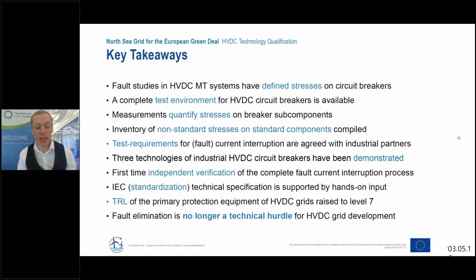And just to repeat, the 3 technologies of industrial HVDC circuit breakers have been demonstrated, which also demonstrates the ability to replicate these fault stresses in the test environment. And this is the first time an independent verification of complete fault current interruption process has been done. And building towards standardization of technical specification, this has been supported with the inputs from all this testing being directly input to IEC working groups and CIGRE working groups.